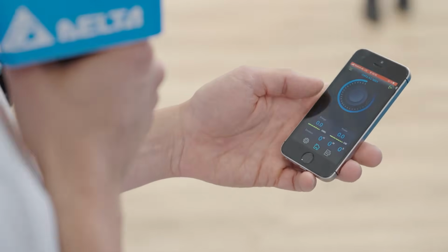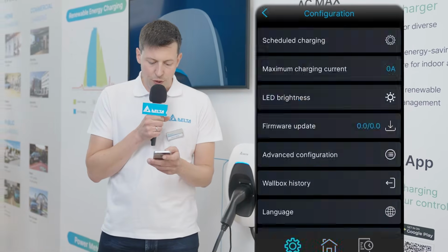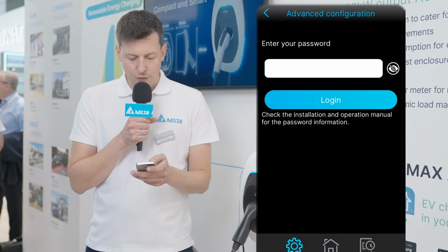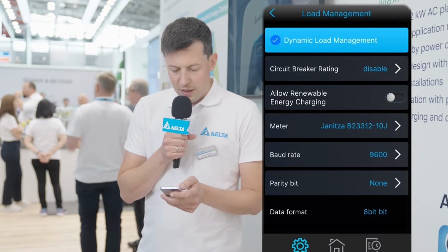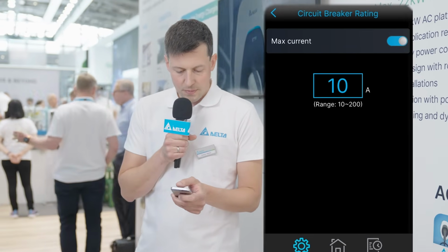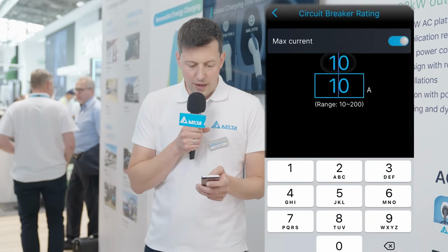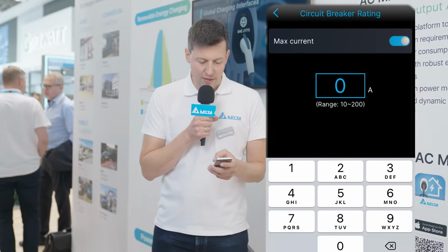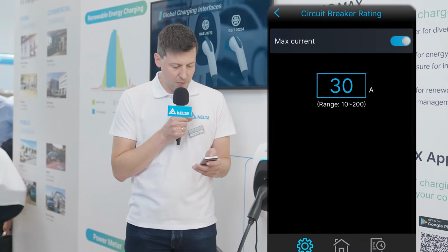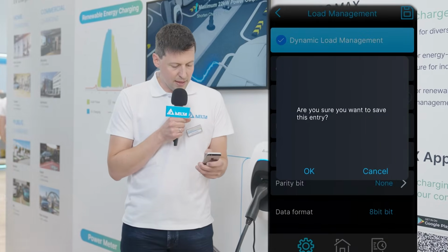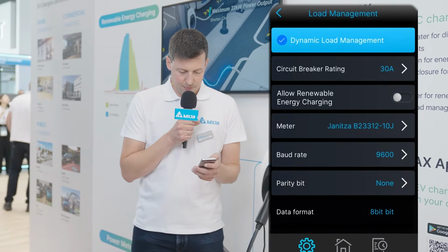To configure the dynamic load management function, we enter the same menu: Configuration, Advanced Configuration, enter the password, and go to the load management submenu. Now we activate the circuit breaker rating and configure it according to the circuit breaker in the installation - let's go for 30 amps here. Go back and save the configuration.